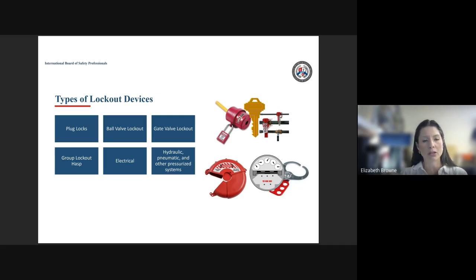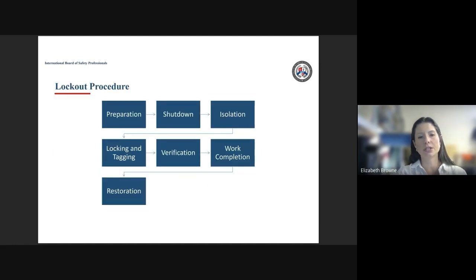But sometimes it's not easy to apply the lock to what you need to. So we have plug locks, valve locks, gate valve locks. There are also group lockout hasps, because every person who is working on the equipment must have a lock on that equipment. There are different types of electrical locks, like circuit breaker locks. And then we also have different types of locks that can go on hydraulic and pneumatic and other pressurized systems. But the general procedure for lockout is that we prepare the equipment for lockout, and then we shut it down. We isolate all energy sources. We lock and tag it out. Then we verify that all energy sources have been eliminated and controlled. And we'll do that by trying to turn the equipment back on.